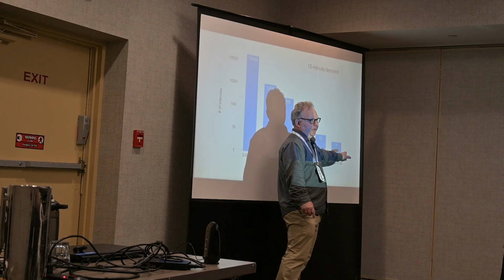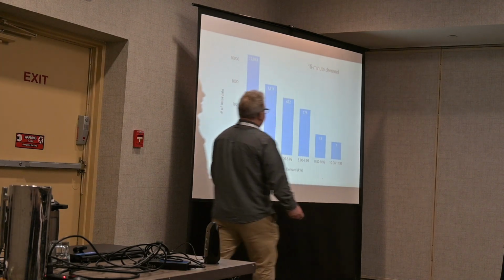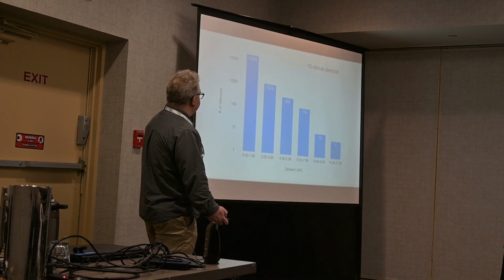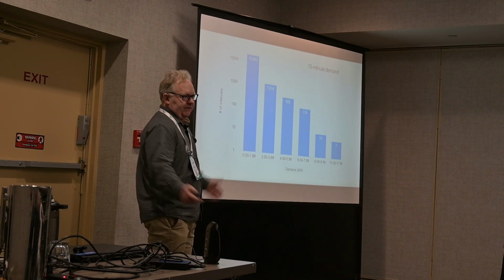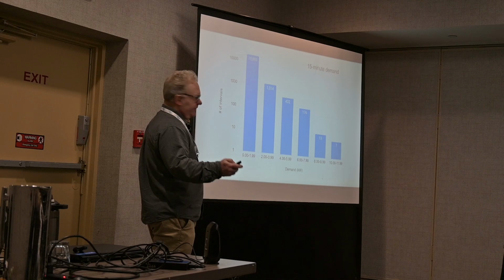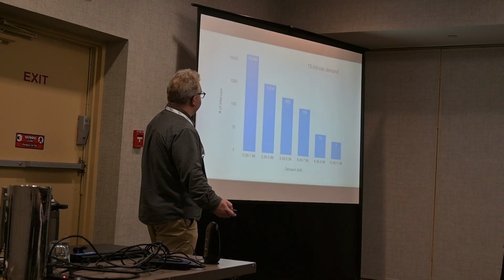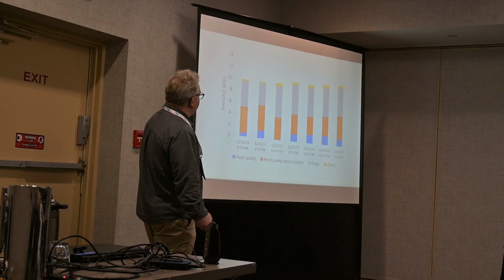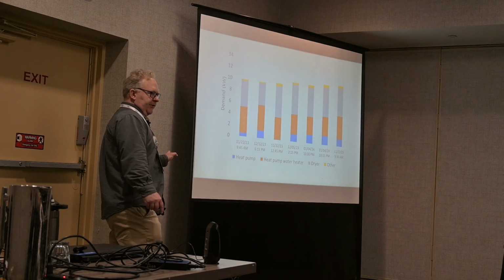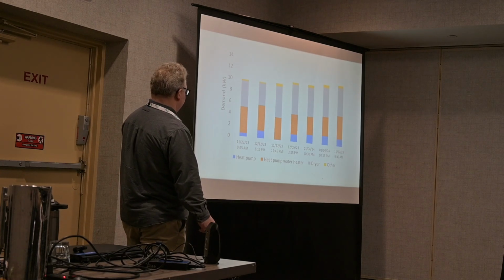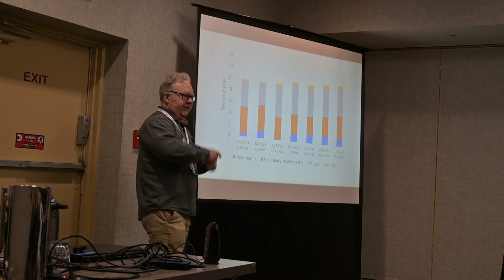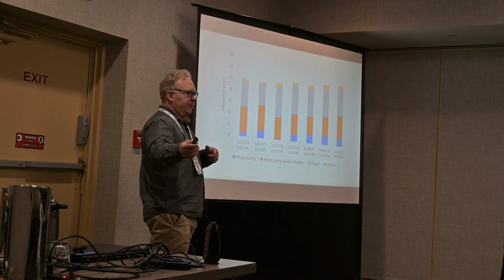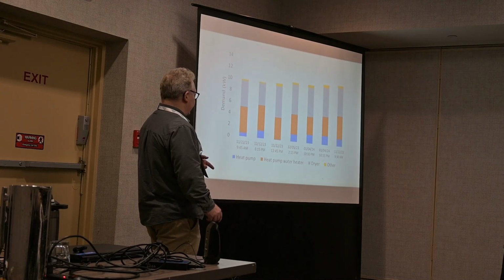Even though I have to base my panel sizing on the peak, this was only 7 intervals out of 22,000. And so this gives you a sense that it's really these rare occasions that are driving the peak demand. I looked at these 7 intervals in a little more detail, and I found that in order to get those really high numbers in excess of 10 kilowatts on my panel, a couple different things had to happen.